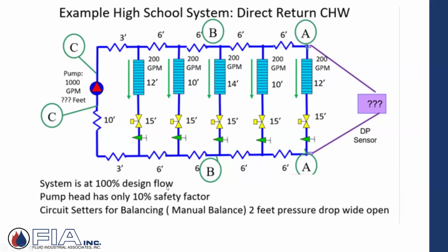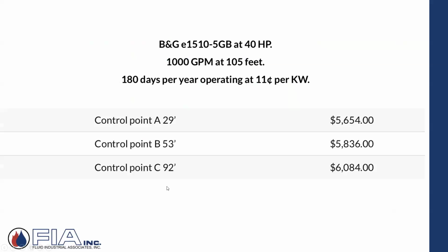So if you're looking for the most energy saving, which is typically what a building owner, client, customer wants, I want to stick it out here. I'm going to try to get that as far out into that system so that I have a greater percentage of variable head loss and only a smaller percentage of control head.